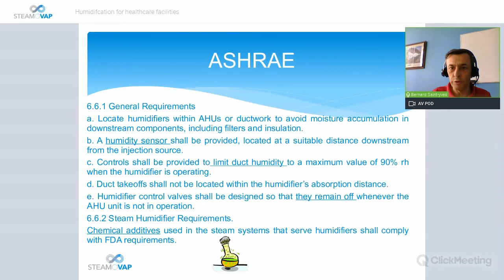For adiabatic, another surprise for us when we went deep into this ASHRAE standard was a mention of water adiabatic high pressure atomizing systems being accepted, which we don't think is a very good way to humidify in healthcare facilities, due to the risk of contamination. For steam, it's only the chemicals that are a concern, but for adiabatic atomizing humidifiers, ASHRAE lists 4 conditions of specific concern. First, a reverse osmosis process plus UV plus a submicron filter.